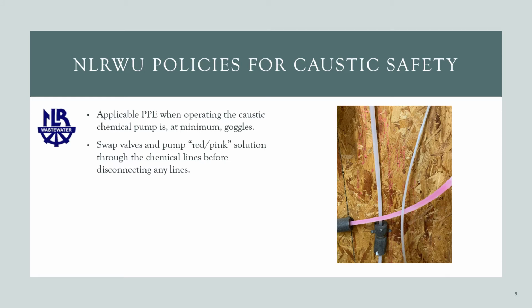Applicable PPE when operating the caustic chemical pump is at minimum your goggles. Swap valves and pump the red and pink solution through the chemical lines before you disconnect any of these lines. While pumping the red solution through the lines does make it safer for you to handle, that does not mean you can't be hurt when handling them. There still may be residual caustic remaining.